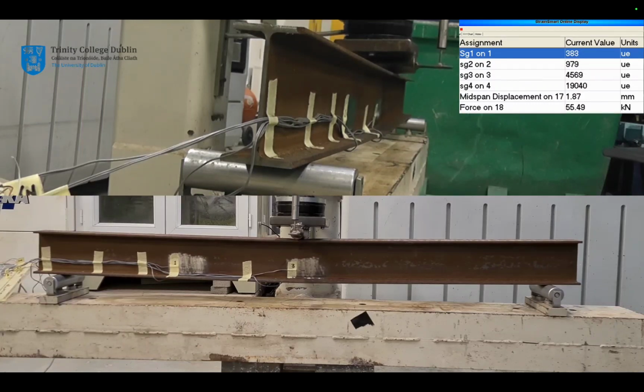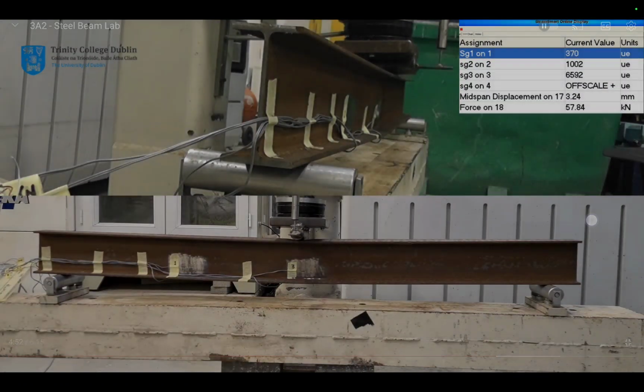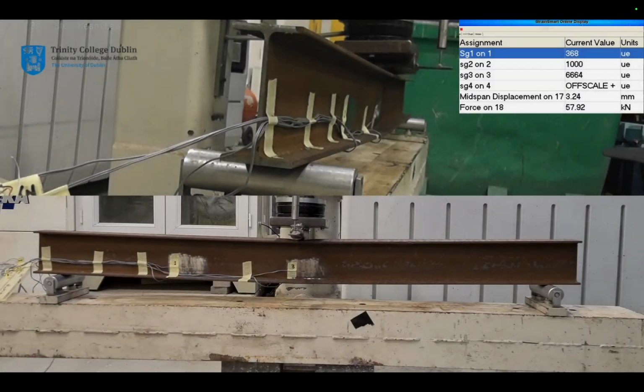Strain gauge 4 has now been overextended and torn. Number four, this results in an off-scale reading that couldn't be displayed. Couldn't read the scale anymore, couldn't measure.